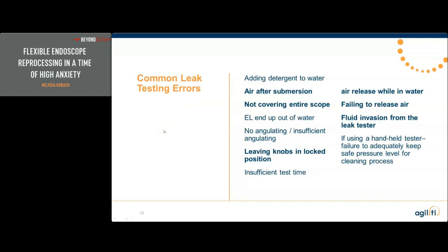Common leak test errors: I see a lot of people who turn the air on after they've already placed the scope in water, which negates the point of doing leak tests, since we're trying to protect it from fluid invasion and want to know if it's leaking because it's an infection risk to the patient.